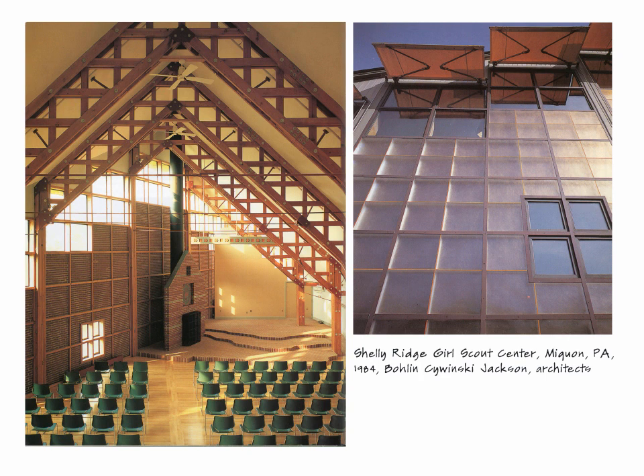Here's an example of a relatively thin plan building — the Shelley Ridge Girl Scout Center in Pennsylvania by Bohlin Cywinski Jackson, a really good firm worth looking at. On the right you see the exterior of primarily a Trombe wall, but it's a combination of Trombe wall and direct gain, with more shading useful over the direct gain apertures. It's a thin mass Trombe wall, only about four inches thick. The idea is that the Girl Scouts aren't using the building late into the evening — it's a daytime use building, so you don't want the heat delayed too long. You can regulate that by the thickness of the mass.